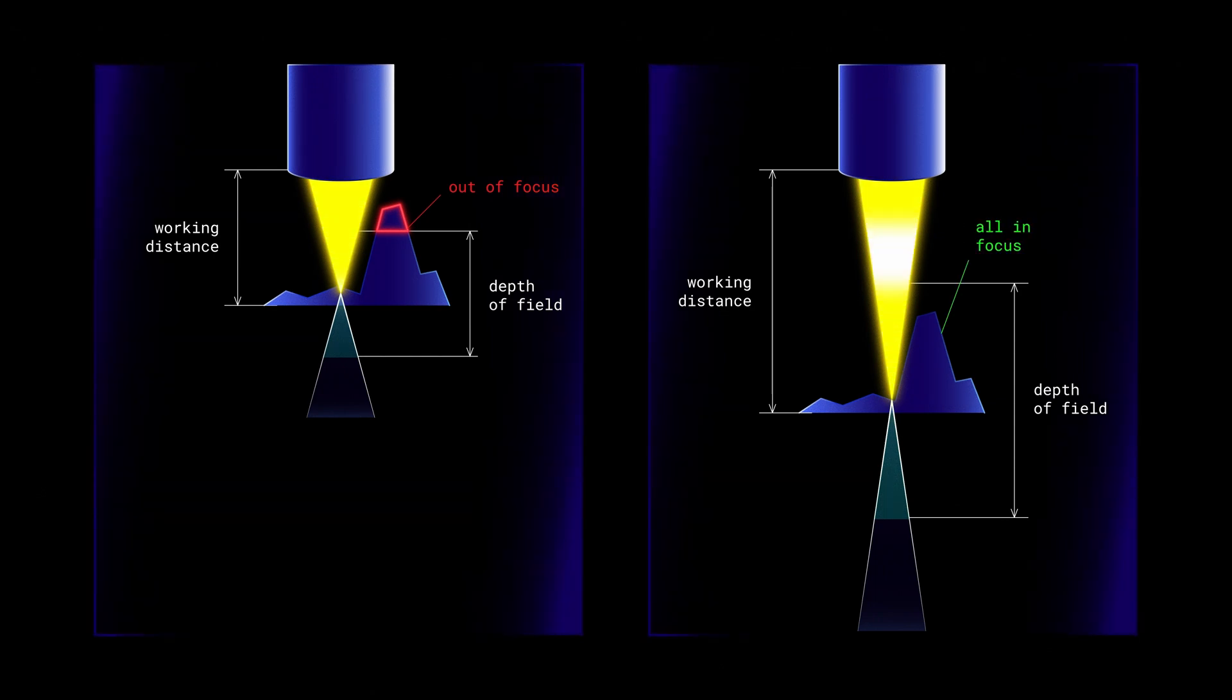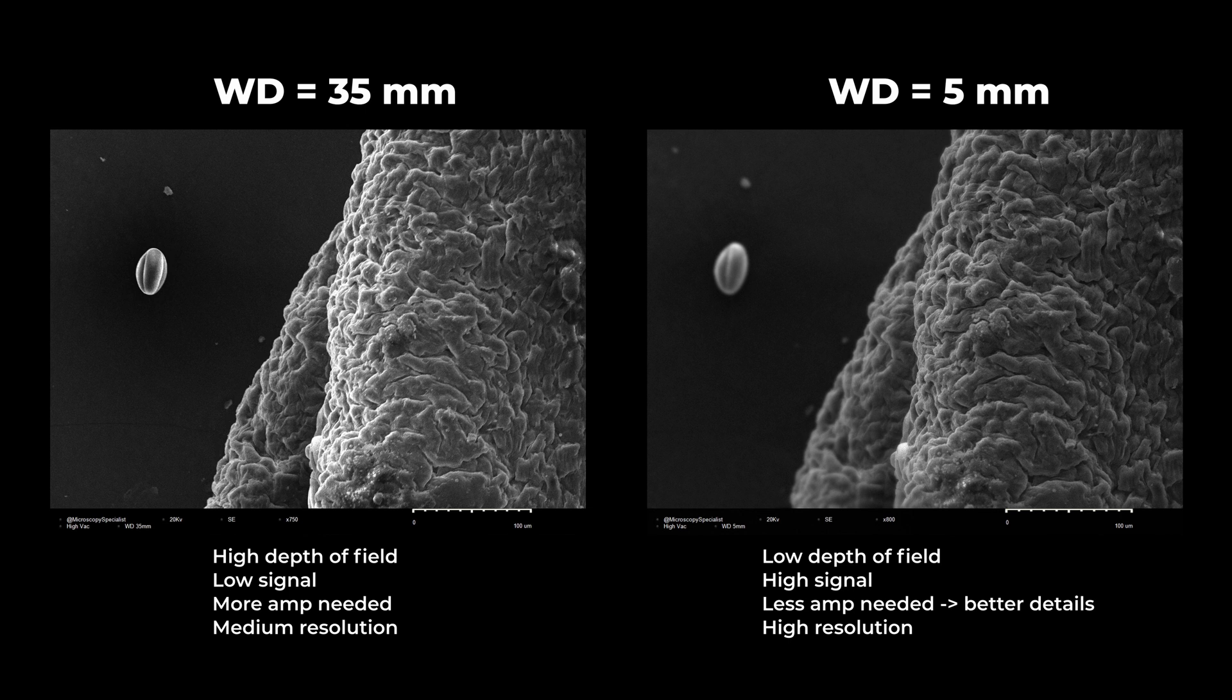When increasing the working distance, we increase the zone along the z-axis in which the spot size will be small enough to produce the in-focus image. Therefore, when increasing the working distance, the depth of field increases.